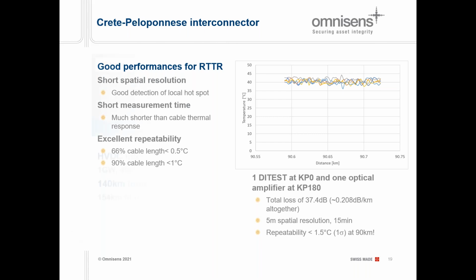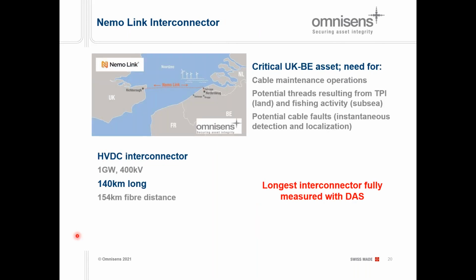More recently, we deployed a DAS system on the Nemo-Link interconnector between Belgium and the UK. It's a massive HVDC, 1 gigawatt, 400 kV cable. The route is 140 kilometers long. The helix factor of the fiber inside the land section mainly and the offshore cable means that there are about 154 kilometers in fiber distance. That is a critical asset between the UK and Belgium, and the users were looking at cable maintenance operations, threats for the land section, fishing and vessel activities for the subsea, and also fault detection and localization. To my knowledge, that's the longest interconnector which is fully measured with DAS as well.